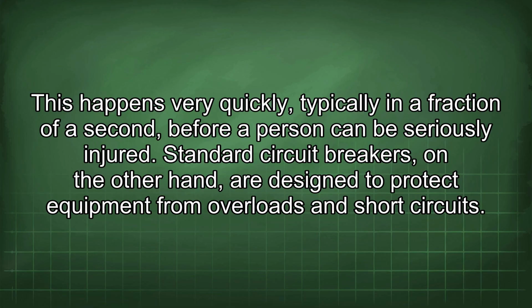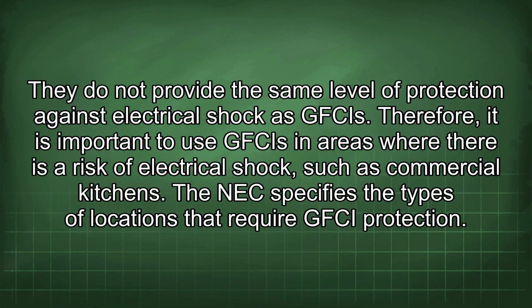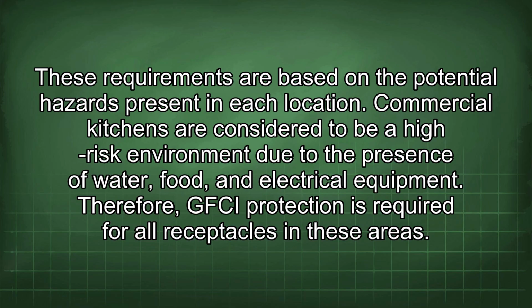Standard circuit breakers, on the other hand, are designed to protect equipment from overloads and short circuits. They do not provide the same level of protection against electrical shock as GFCIs. Therefore, it is important to use GFCIs in areas where there is a risk of electrical shock, such as commercial kitchens. The NEC specifies the types of locations that require GFCI protection. These requirements are based on the potential hazards present in each location. Commercial kitchens are considered to be a high-risk environment due to the presence of water, food, and electrical equipment. Therefore, GFCI protection is required for all receptacles in these areas.